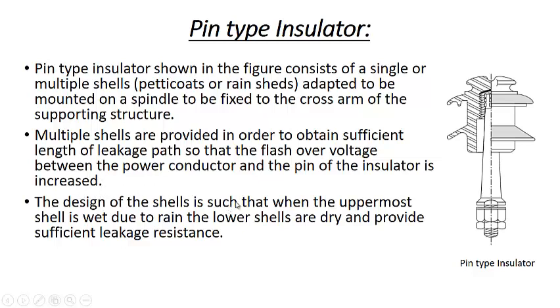The design of the shells is such that when the uppermost shell is wet due to the rain, the lower shells are dry and provide sufficient leakage resistance. Because due to the rain, the dielectric strength will decrease, because rain itself may be conducting in certain conditions. Since the lower petticoats remain dry, they are capable of still providing a good dielectric strength or leakage resistance.